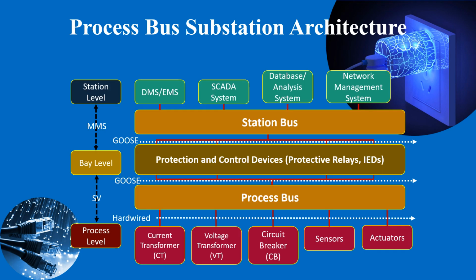The IEC 61850 standard defines a communication architecture ranked into 3 levels, and these are the station, bay, and process level. The station level is used for archiving information, monitoring data storage, control operations, and management software tools. This level carries information from SCADA and protection relays from the bay level, and the devices present on this level are the station computer, HMI, SCADA system, and RTU. The bay level consists of different IEDs. The IEDs can make local control decisions, protect against irregularities from the process level, transmit data to other IEDs, or send data to the substation SCADA for further processing and monitoring. The process level contains devices such as circuit breakers, primary and secondary switchgears, actuators, and others. So these are the measurements coming from the different parts of the substation.